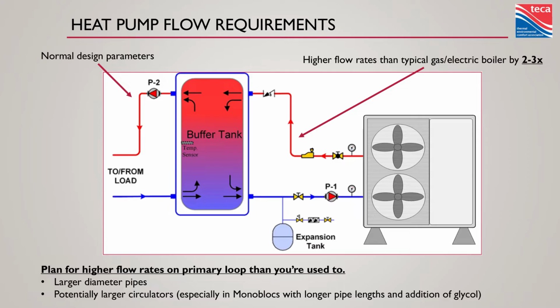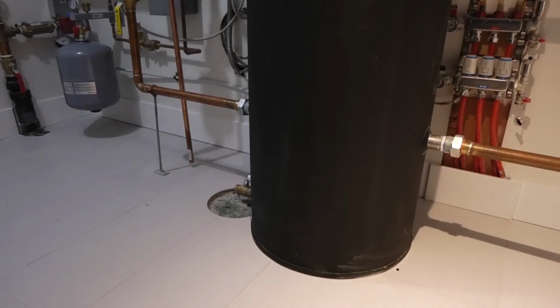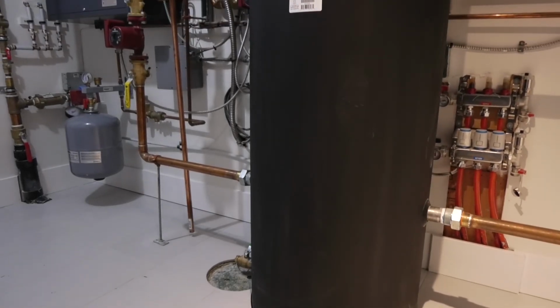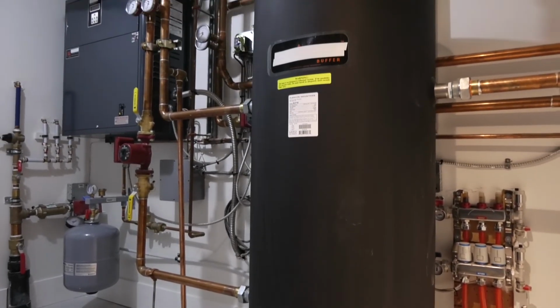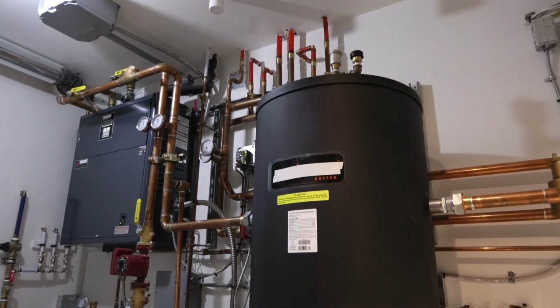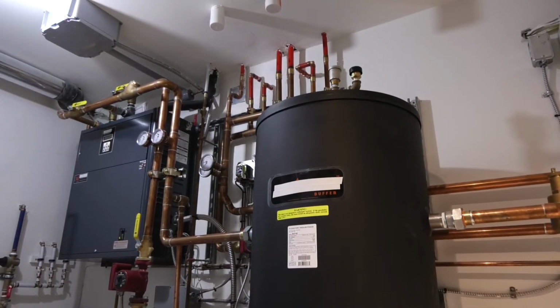If we do primary, secondary piping, we're going to have some successful systems because we can make sure those heat pumps get the flow they want. Some of the most challenging, I'll nicely say, air-to-water heat pump systems I've been involved with were ones that were direct piped, where we were trying to get the kind of flow rates through the heat pump that they needed through the entire system. It wasn't designed for that. We're used to 10 or 20 degree delta T's in our radiant floor panels and things like that. We're dealing with like 3 to 9 degree delta T's on our heat pumps here. We're just not sizing our heat emitters that way. We're not sizing our pipes that way, and we don't have to.